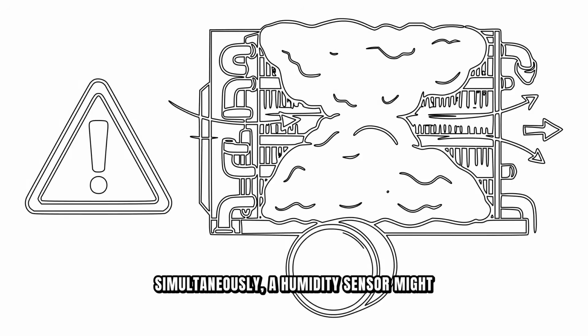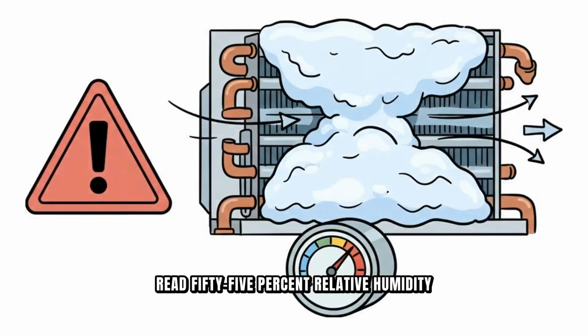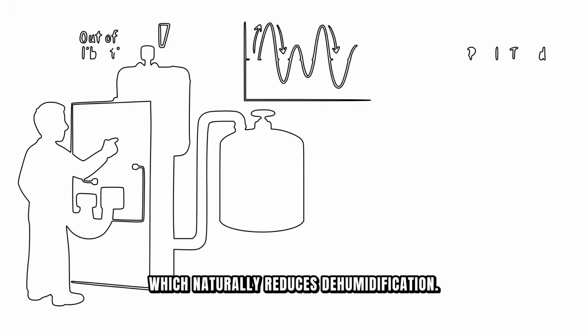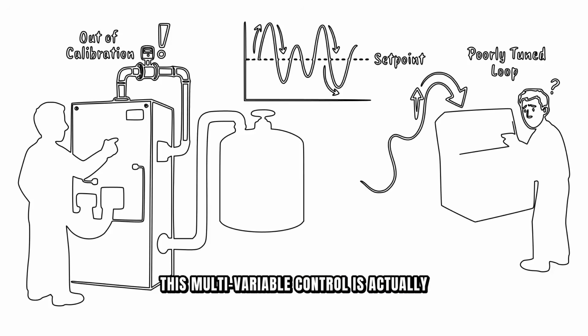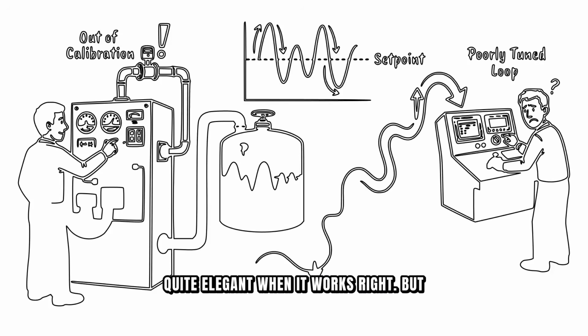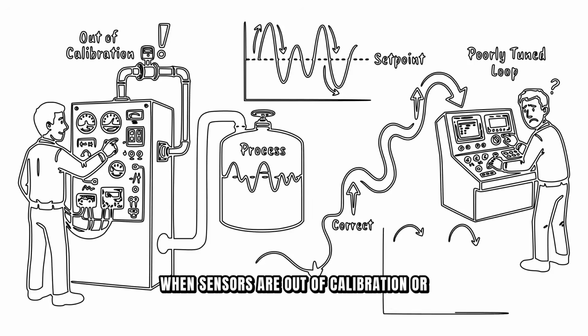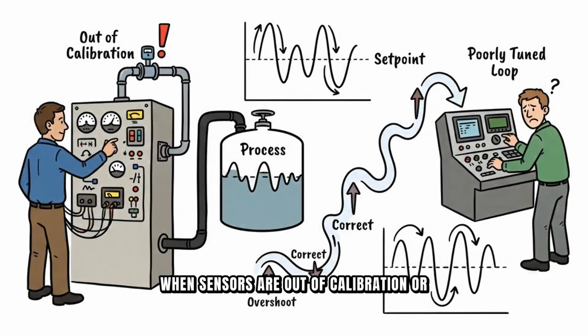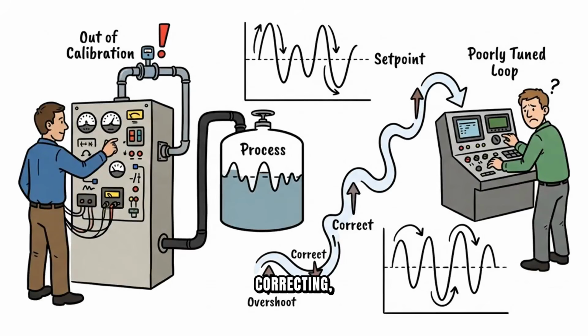A humidity sensor might read 55% relative humidity, while the set point is 45%. The system reduces chilled water flow to let the air warm up a bit, which naturally reduces dehumidification. This multivariable control is actually quite elegant when it works right. But when sensors are out of calibration or control loops are poorly tuned, you get hunting, where the system keeps overshooting the set point and then correcting, creating discomfort and wasting energy.